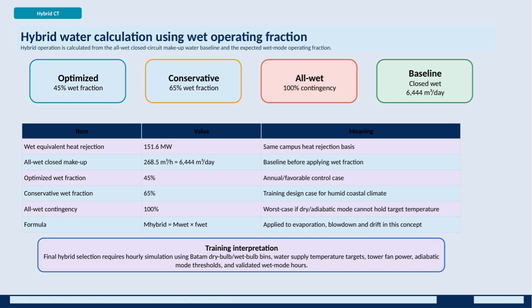The critical formula guiding this is M hybrid equals M wet times F wet, meaning the hybrid water use equals the baseline wet water use multiplied by the fraction of wet operation. This formula is applied across evaporation, blowdown, and drift losses within the system. Ultimately, selecting the final hybrid cooling strategy requires detailed hourly simulation using local climate data, like the site's dry bulb and wet bulb temperature distributions, water supply temperature targets, cooling tower fan power, and validated wet mode hours. This approach ensures a cooling design is both effective and water efficient under specific site conditions.